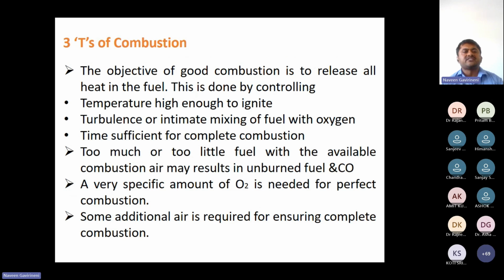These three T's play a vital role for good combustion. If we do not get good combustion, we do not get good steam, and we do not get exact optimization of the fuel either. For that purpose the three are important: temperature, turbulence, and sufficient time. Too much fuel, and too much air, is also very dangerous. That will lead to unburnt fuel, and there is a chance of blasting of the boiler due to CO formation. If you give more excess air, more oxygen, so much heat is transferred to the atmosphere, and that is a fuel loss.